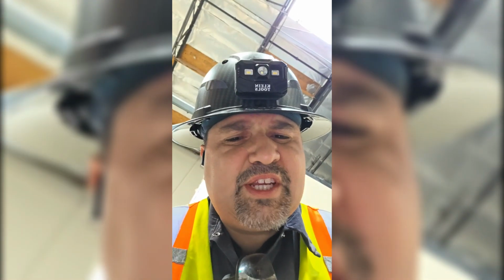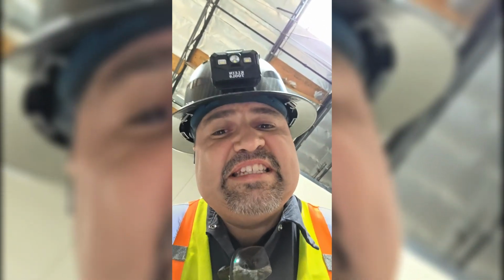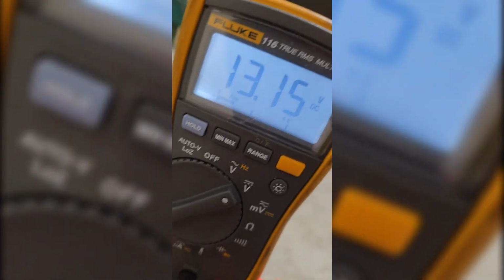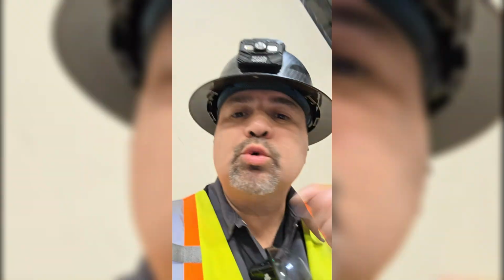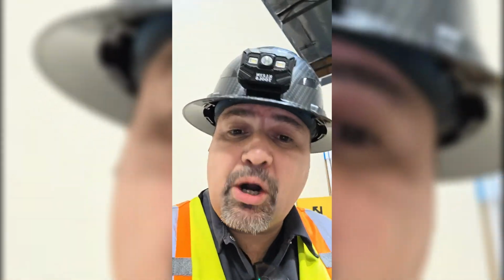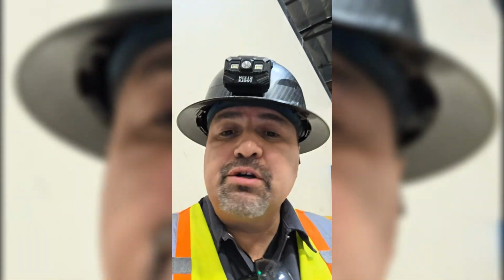So we either got 2, 6, or 12 volt batteries. Let's check it out. DC. Got my probes locked on, and we're reading 12 volts. Okay, so it looks like both batteries are reading 12 volts, so we have 2 12-volt batteries. They can either be run in parallel, which gives you 12 volts, or in series, which gives you 24 volts.